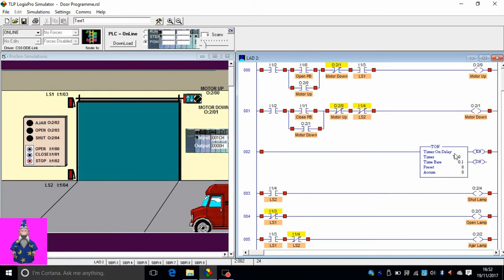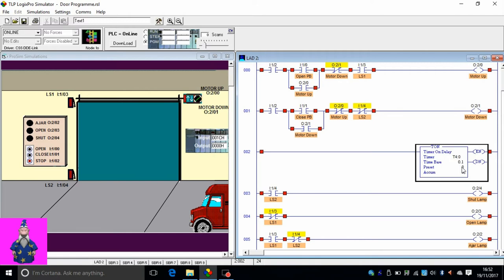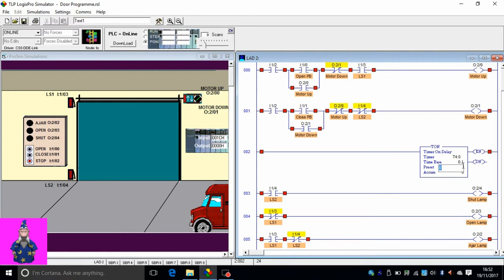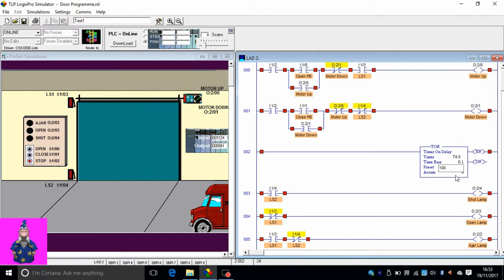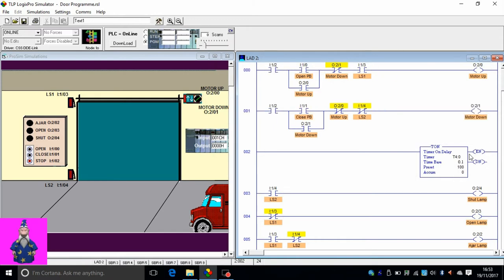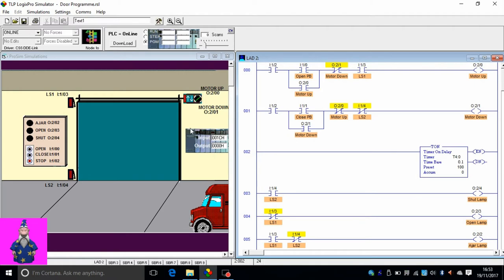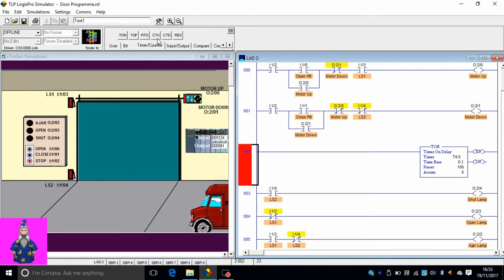The length of the timer, how long it will be on, you can set. The time base is 0.1. If I wanted 10 seconds, then I'll put 100 here. 100 times 0.1 is 10 seconds. That's how you calculate how many minutes or seconds you want it on. After 10 seconds, it'll be energized, it'll be done.